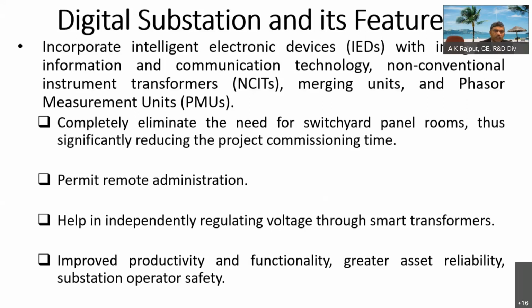Generally we measure the voltage, current, and the frequency or the power factor. Phasor measurement units also measure the phase angle, and it helps in better diagnosis of the fault conditions. We can also predict how the system is going to behave when we are talking of real-time operation of the system. So it completely eliminates the need for switchyard panel rooms, thus significantly reducing the project commissioning time. It permits remote administration, that is remote operation. It helps in independently regulating voltage through smart transformers, with improved productivity and functionality, greater asset reliability, and substation operator safety also ensured.